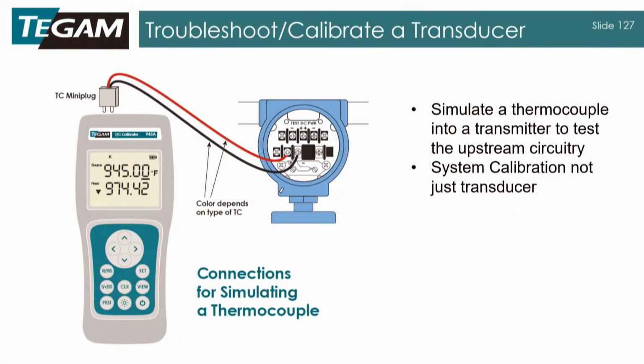The other thing you can do with this, of course, is that this is typically hooked up to some of the control system. You can set this in these calibrators, not just ours, but many of them. You can put them in a stair-step mode, and it'll go through 10 steps. You can leave that on a transducer. You can go over to the control area and see how the whole system is responding. We have a distributed control system or whatever it's operating with, or even a panel meter somewhere, whatever you have.